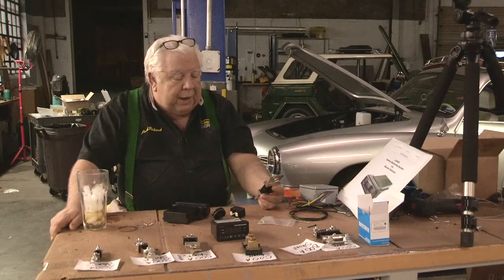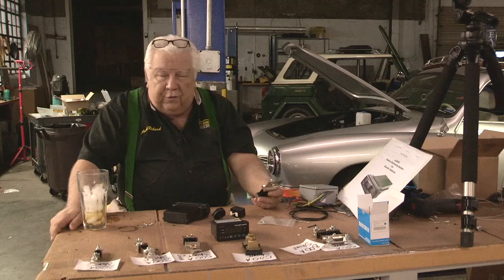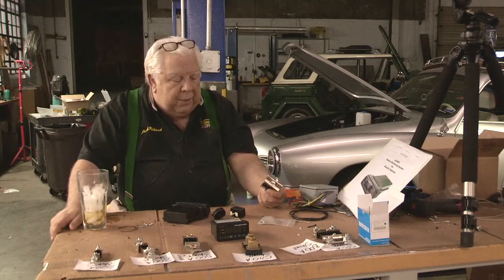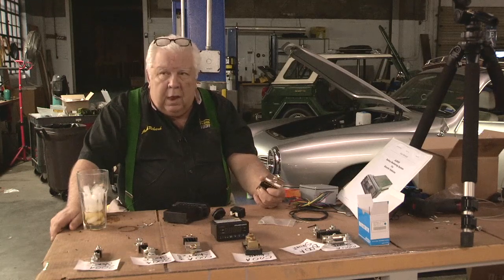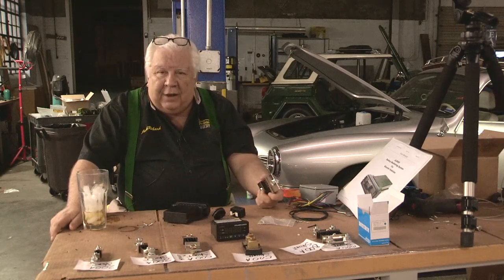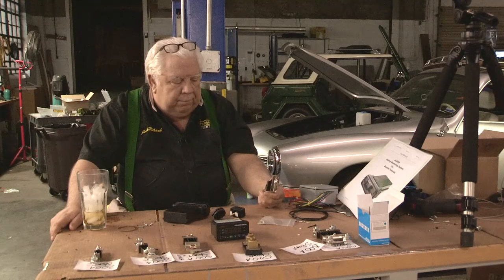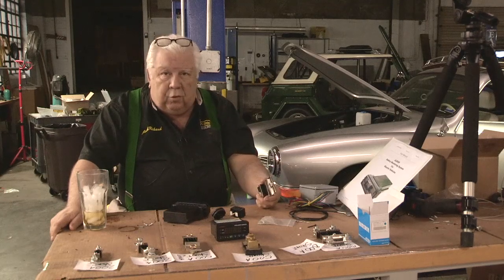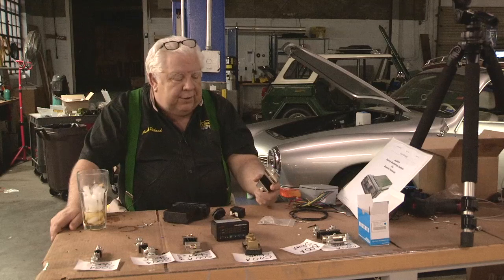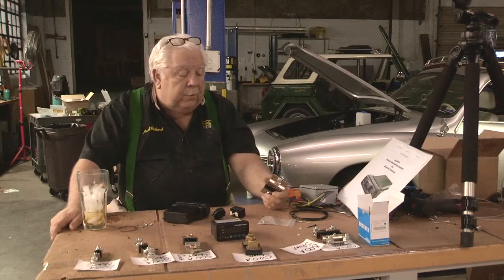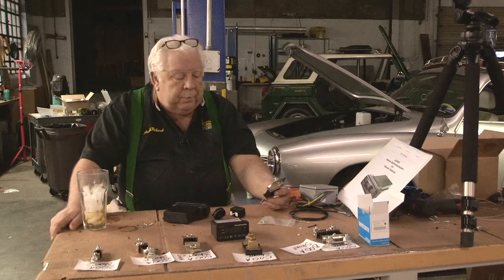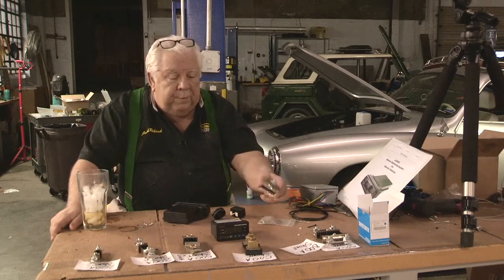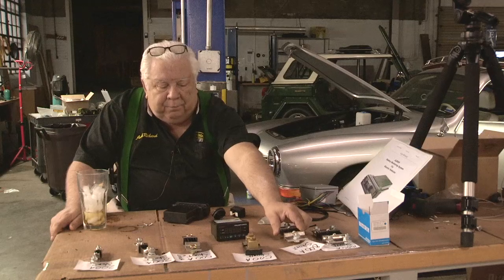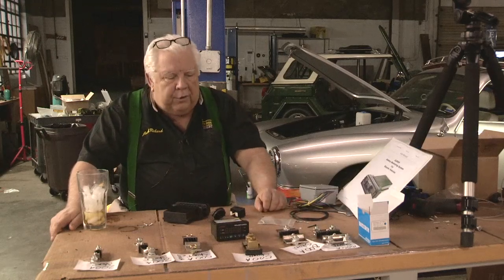They have developed a metal called manganin, which is an alloy of manganese, copper, and nickel. Because the three metals expand or react differently to temperature, and their conductivity changes in different directions with regards to temperature, it kind of cancels out the thermal effect. And so most modern shunts are made from manganin and are a very small value.